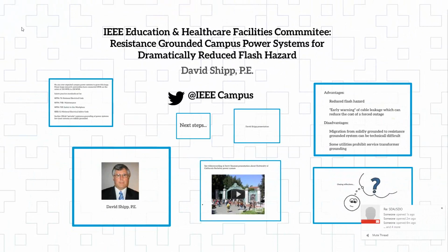I don't think we're able to do that with the Mott Children's Hospital, but I know we've advanced the idea, for long bulk feeders for lighting, of using step-down transformers to trap the zero sequence current, for example. But it's just design practice. The architect engineer retains an electrical engineer who may or may not be skilled in understanding. You know, you can save a lot of money not carrying the neutral, and not only that, you can start partitioning some of your arc incident energy if you do it that way. It's easier to do that in a fresh new building, and we've advanced that and kicked that idea out there. We don't always see it in bidding documents, do we, Jim?